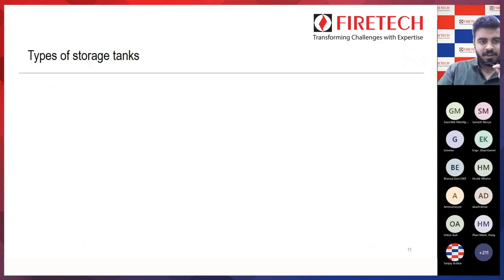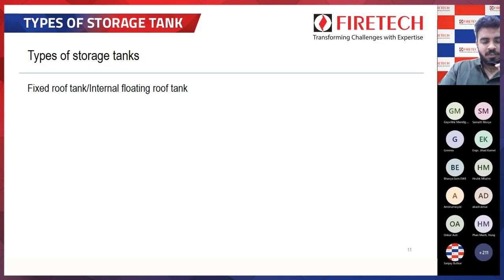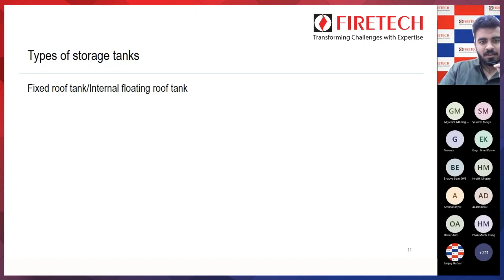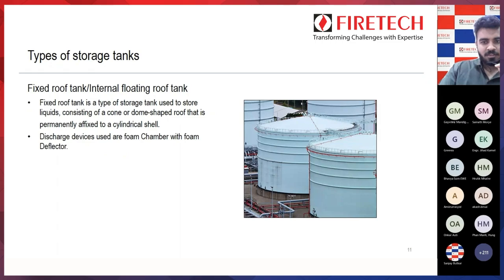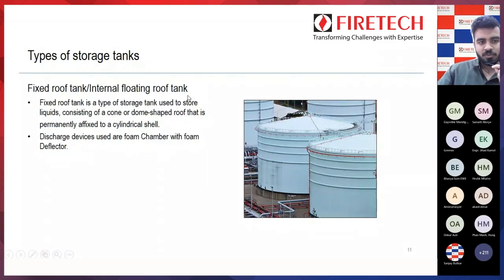Moving ahead, we will understand the types of storage tanks. First is the fixed roof tank or internal floating roof tank. This is a fixed type of tank with a cone roof permanently affixed — it is not a floating type. The discharge devices used here are foam chamber with foam deflector. This can be called a fixed roof tank or internal floating roof tank.